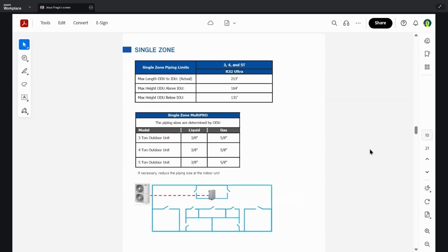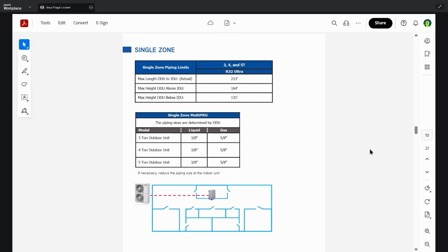Moving on here. This is our single zone piping limitations. This chart pretty much gives us the max length ODU to IDU, the max height ODU above IDU, and max height ODU below IDU, and we know those values are 213, 164, and 131 feet.